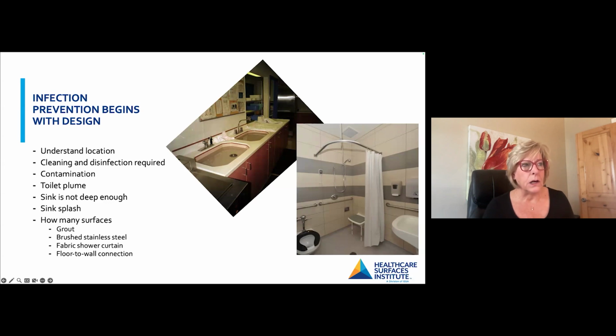So what we did here is, number one, they chose a solid surface material, and you can see the pretty pink band there. They used that to make the sink significantly deeper so that the splash wasn't an issue any longer. So again, surfaces can be used to solve an issue, and wet counters, delaminated counters, etc., can create incredible microbial reservoirs, and pathogens can live and breed in those areas. So these are just a couple of issues that exist.